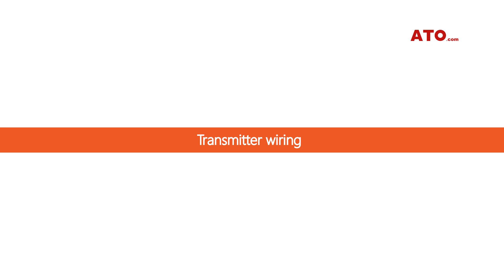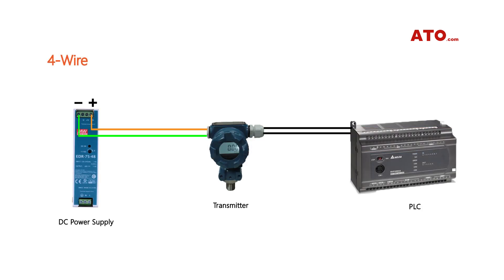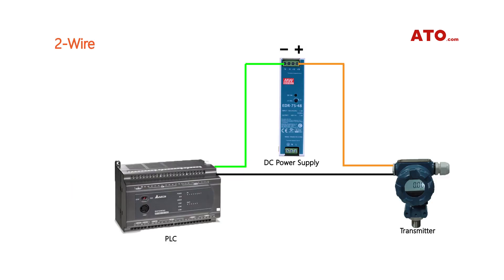Transmitter wiring methods: The first is the 4-wire wiring method, where two power lines are connected to the transmitter and two output lines are connected to a display device or control device. The 2-wire transmitter forms a loop with the controller, and the detected data can be directly transmitted to the controller with a wire.